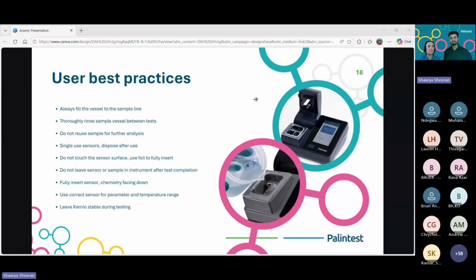Now, this is more for care of the instrument. As you can imagine, it is a portable device that you are carrying around. There are chemicals in there. If you pick up that device with the water sample still in there, although the instrument is IP67 rated, if it's left for a very long time, it could cause damage to the contact pad. So it is just wear and tear and general care and maintenance of the instrument. Also, fully insert the sensor as shown in the demonstration, use the correct sensor for each sample and temperature type, and leave the Kemio stable during testing.